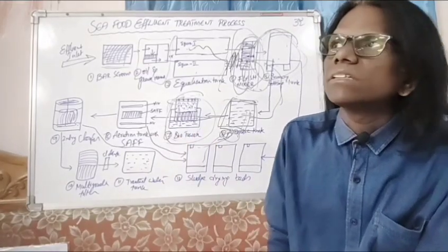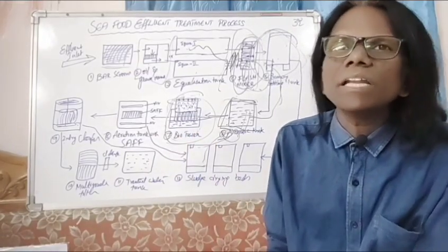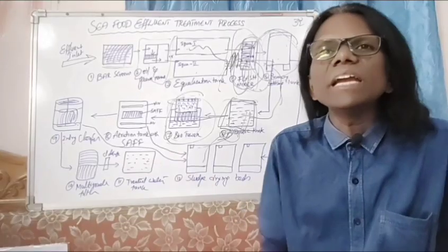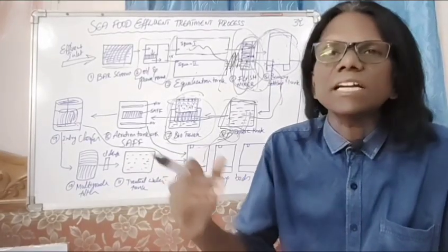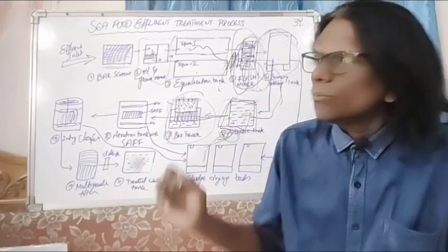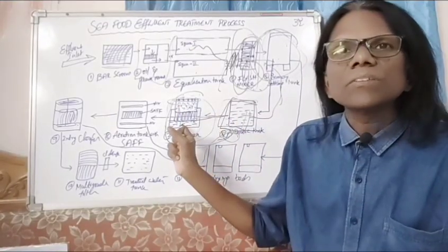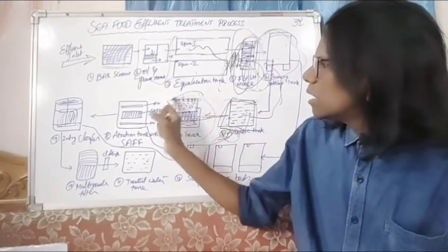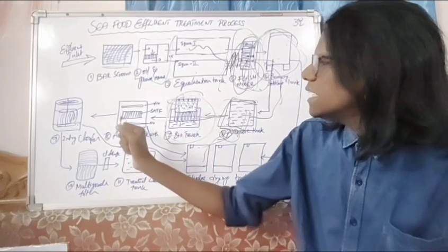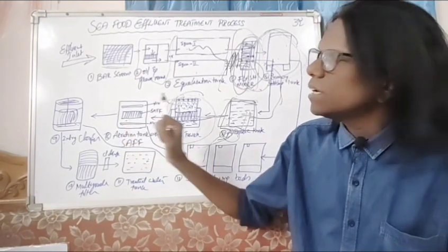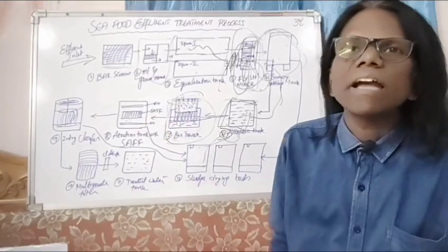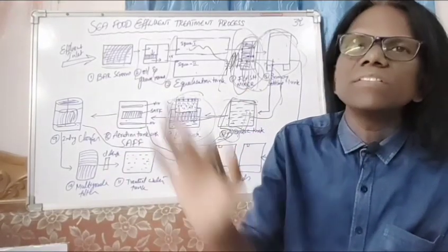Sometimes there is no production for more than a week or 10 days. We have to make sure that during lengthy shutdowns of more than a week, we add feed to the biotower as well as the aeration tank. We have to make sure there is continuous feed flow to the biotower as well as the aeration tank at least once a week during a lengthy shutdown period.